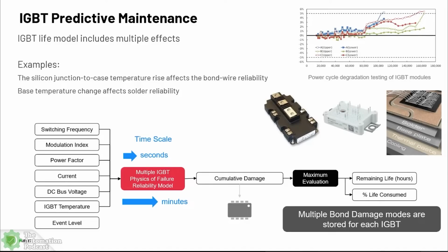Well, I can't go do a visual inspection, because this is what an IGBT looks like - I can't really look under the hood of that. So instead, what we've developed is our own predictive maintenance models to understand when that component is going to be near the end of its life. The way we do that is through something called a physics of failure reliability model.